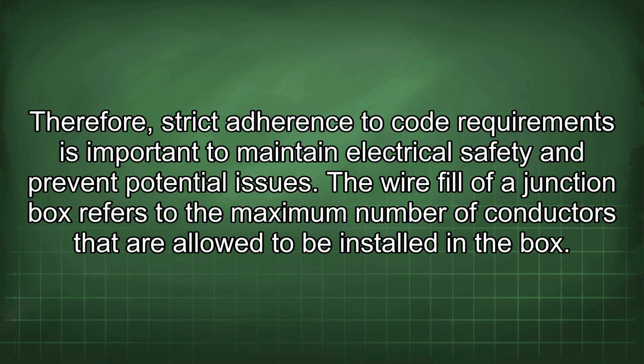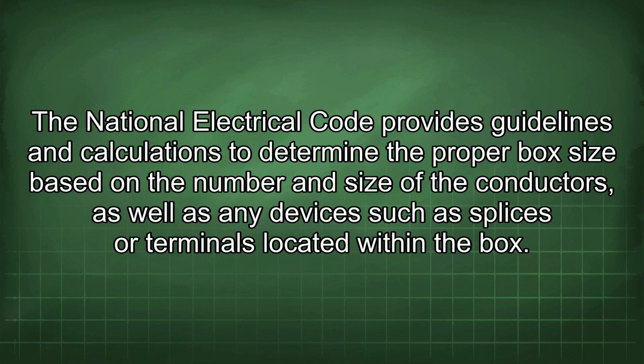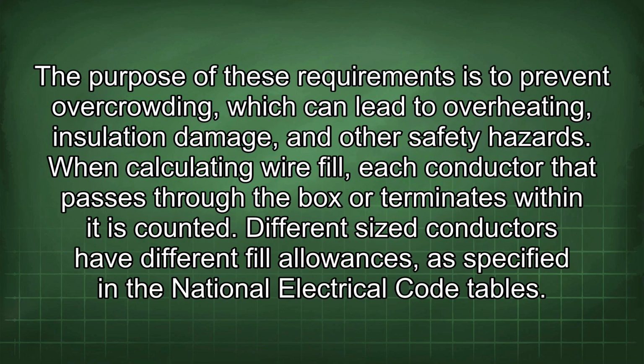The wire fill of a junction box refers to the maximum number of conductors that are allowed to be installed in a box. The National Electrical Code provides guidelines and calculations to determine the proper box size based on the number and size of the conductors, as well as any devices such as splices or terminals located within the box. The purpose of these requirements is to prevent overcrowding, which can lead to overheating, insulation damage, and other safety hazards.